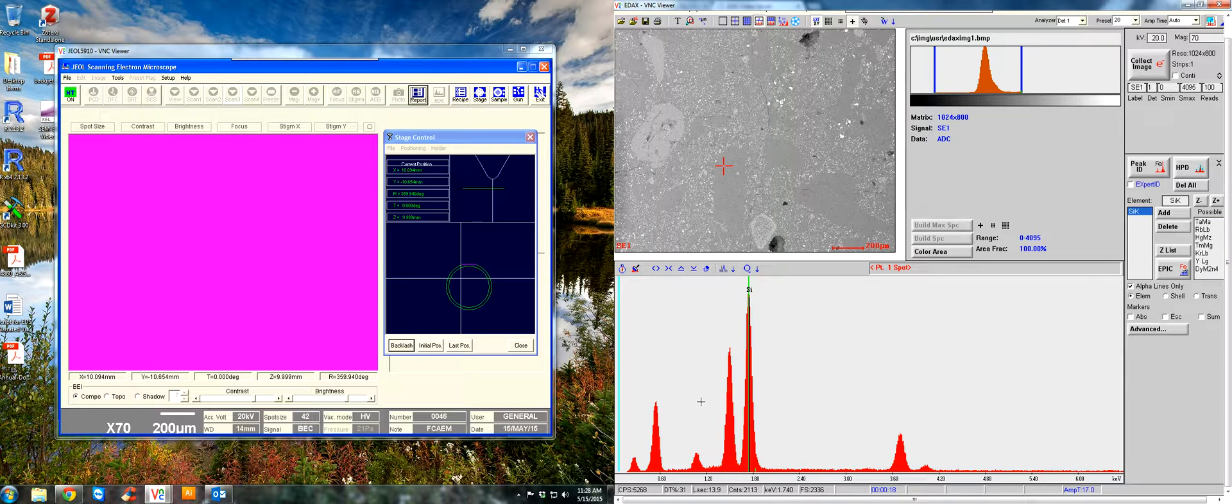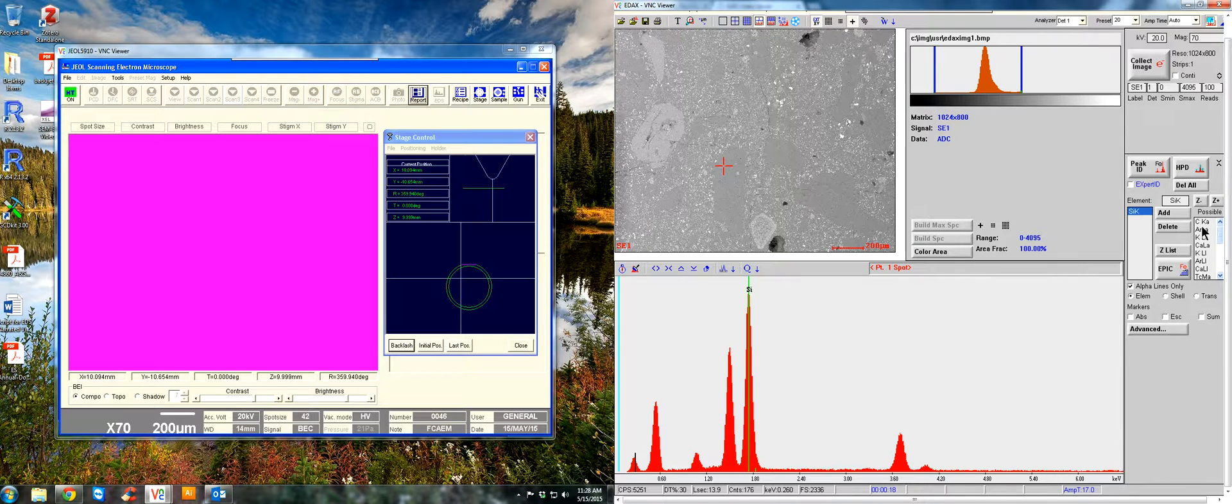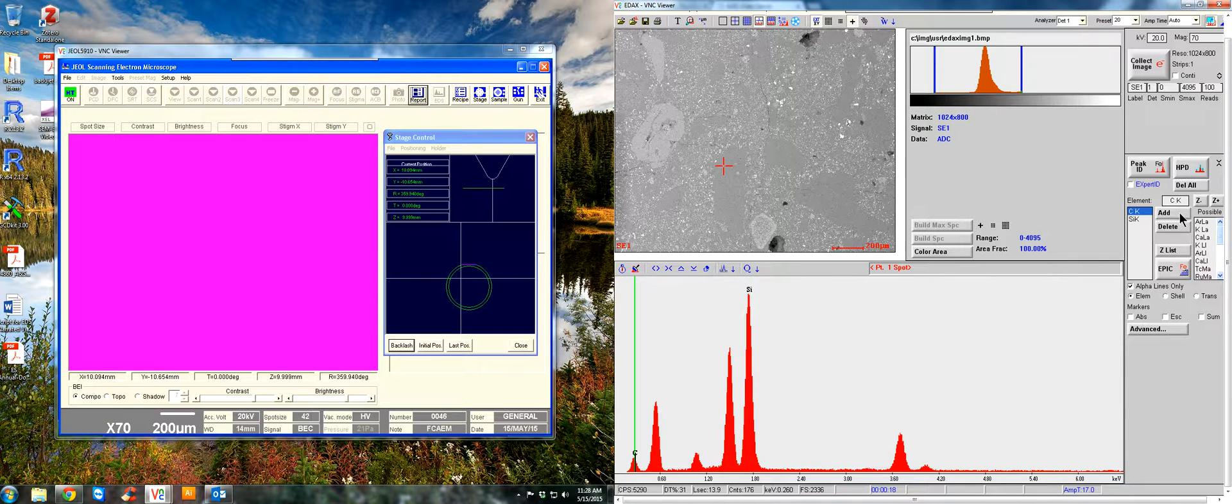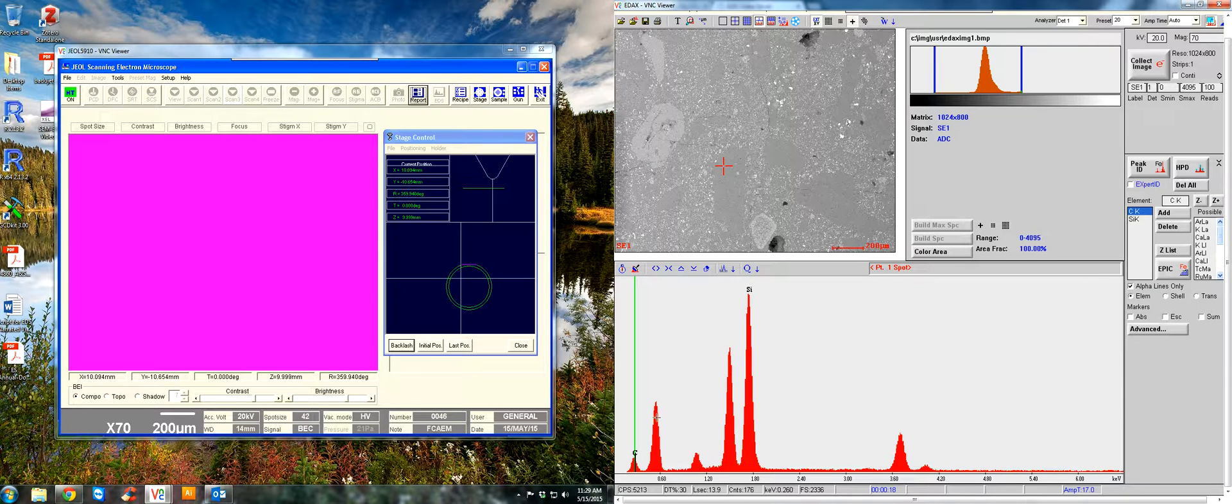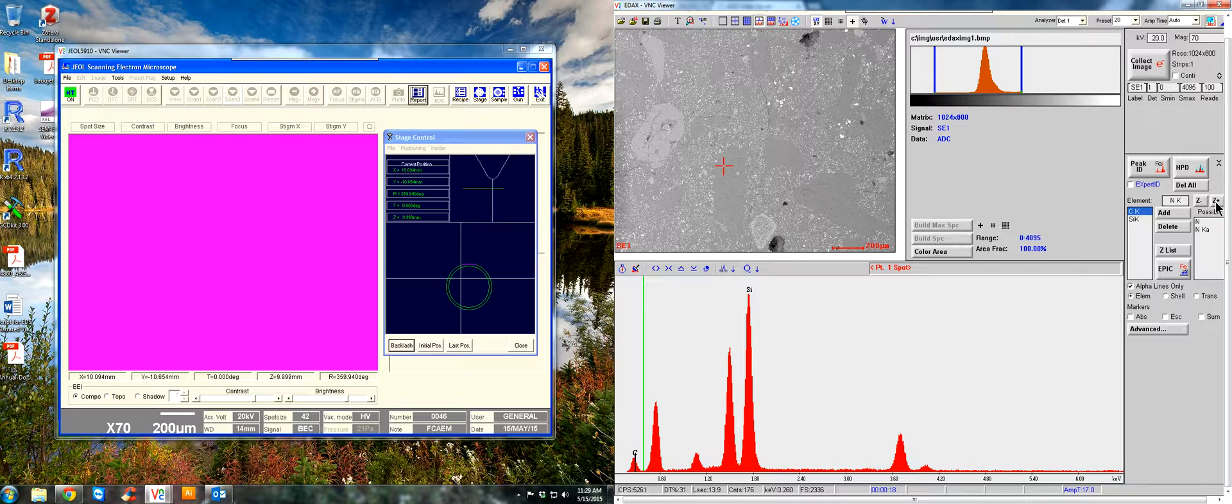Okay, then you can go over to, let's start with this one, this peak over here, really low energy. That looks like a carbon K-alpha peak. Now, carbon's present in the sample because this thin section is carbon-coated. Okay, what you can also do, too, is these buttons, Z-plus and Z-minus. This is going up in atomic number from carbon. So the next element would be nitrogen.